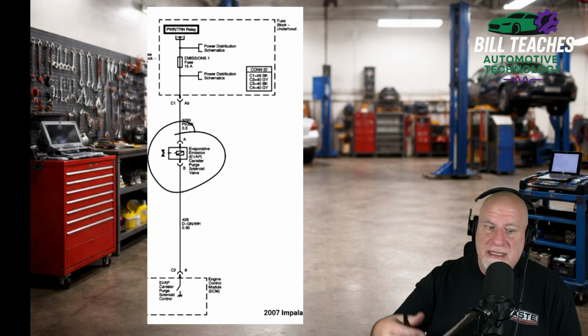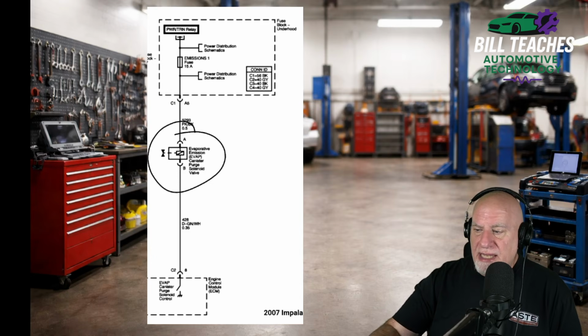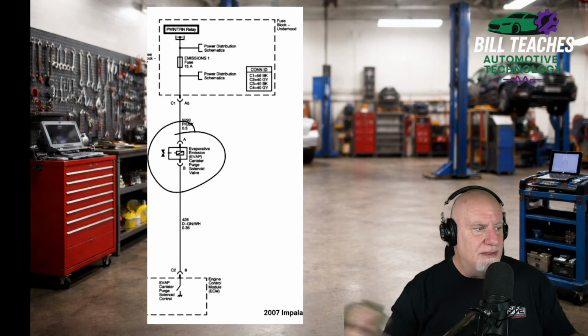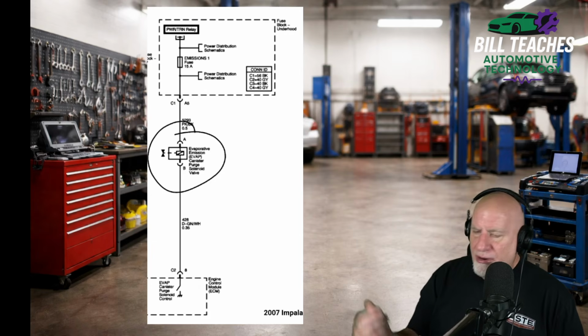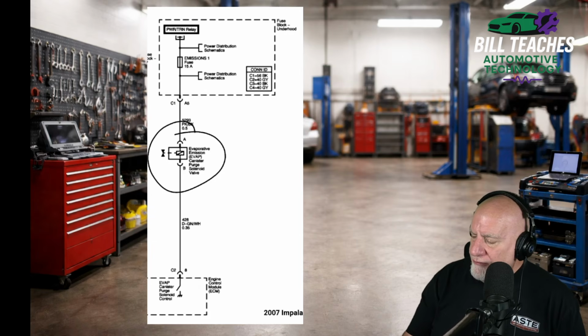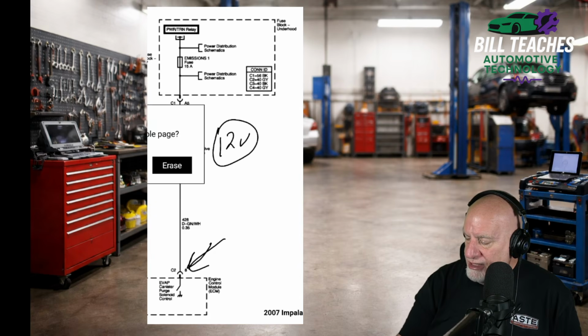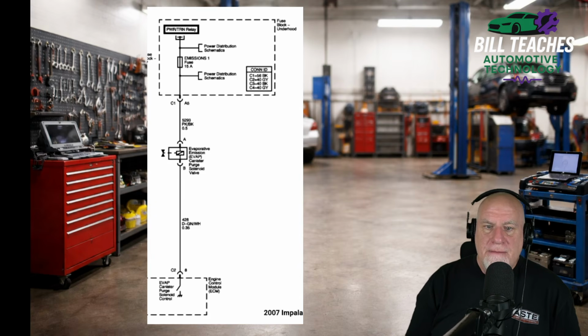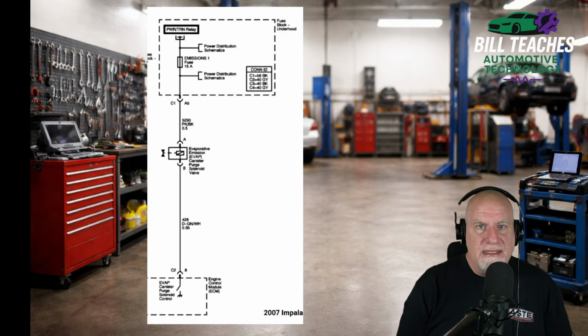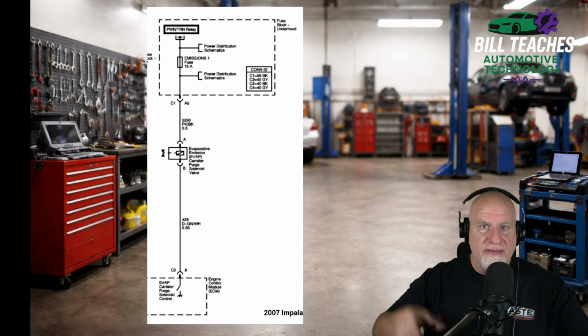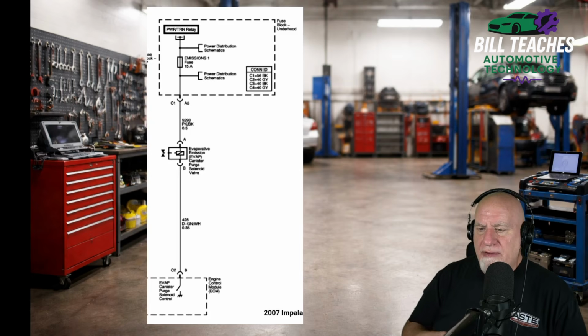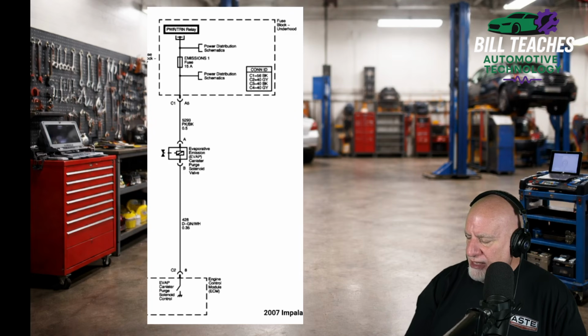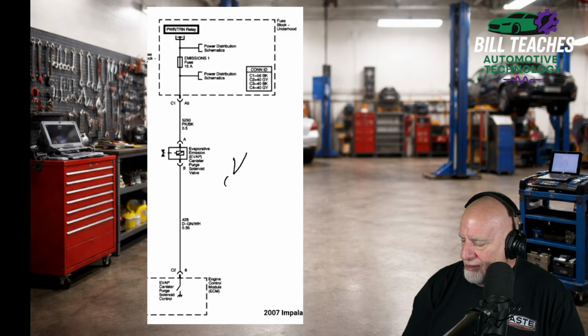A lot of techs at this point, especially new techs, are going to say, yes, Bill, we've got a bad part. Throw the part on there. So what if we have a bad connection somewhere? We're just going to do a quick voltage drop test. Now, to do a voltage drop test, the system has to be active. It's got to be turned on. So I would recommend turning it to 100% duty cycle.